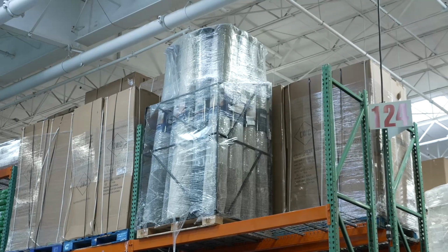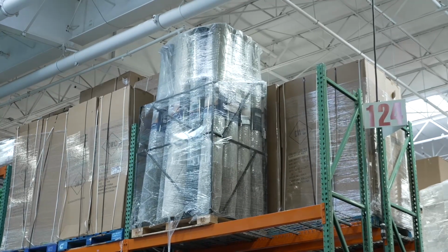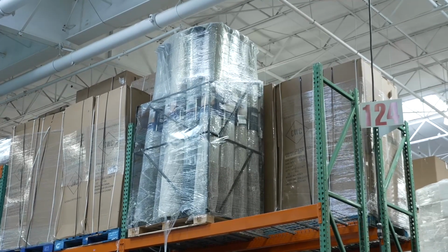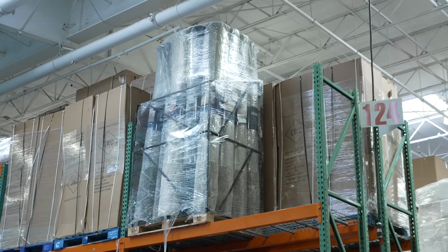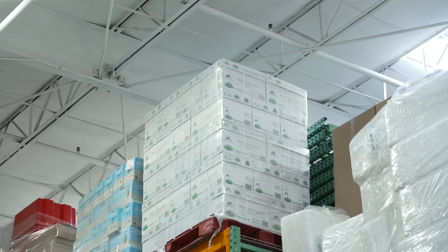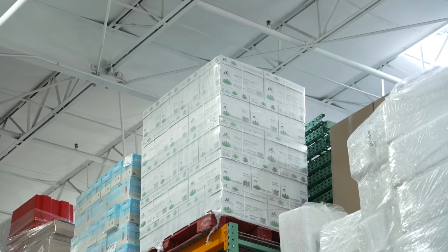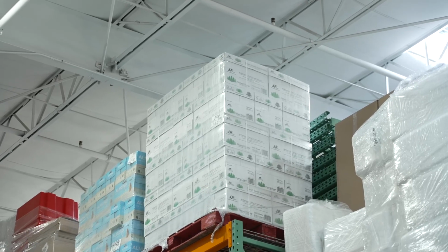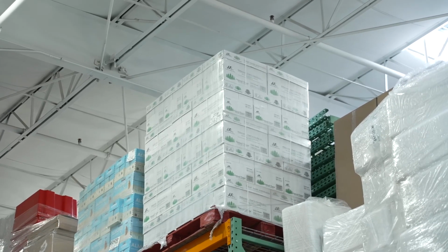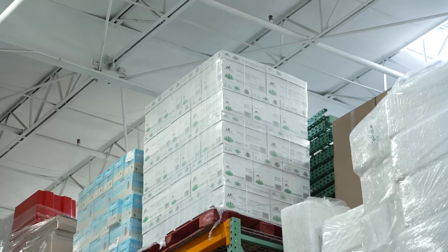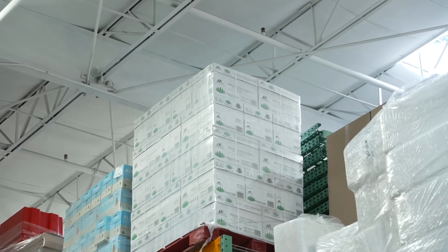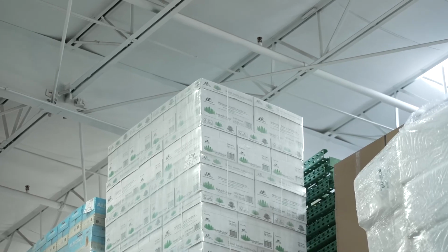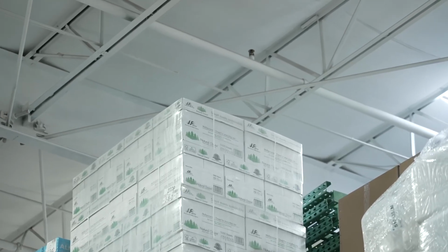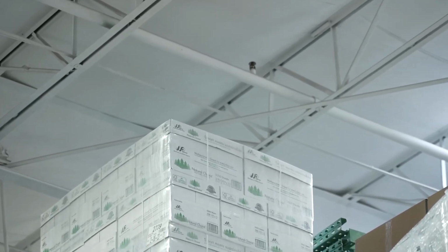In this particular case here, you have racks that are set up and they're sufficiently below the sprinkler system for it to operate effectively. Now we have some encapsulated pallet product that's on the upper shelf. One of the things as you're doing your engine company inspections is to make sure that it's not obstructing the sprinkler discharge. In this particular case, this is appropriately distant, which is a minimum of 18 inches from the sprinkler head above it.